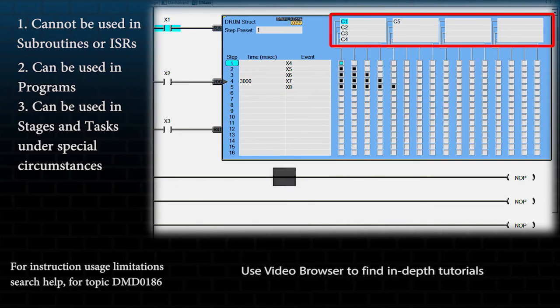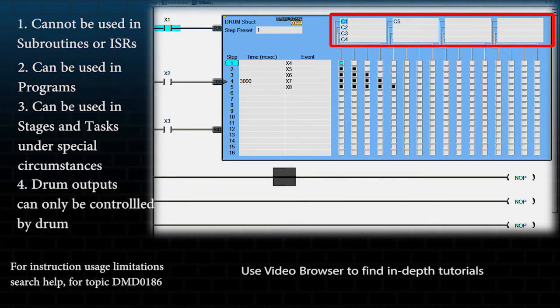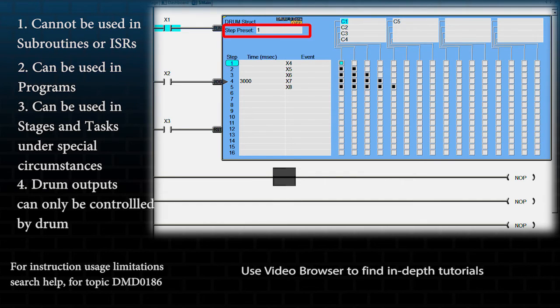Any outputs that you place in the drum will be controlled by the drum when the PLC is in run. So do not try to control any of these outputs elsewhere in your program. The step preset is the step on which the drum will start when enabled or reset.